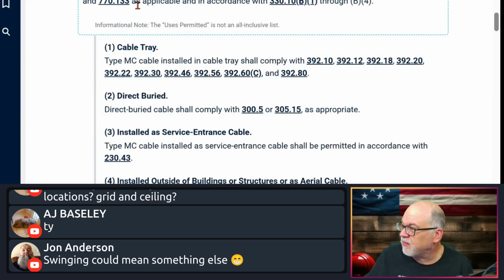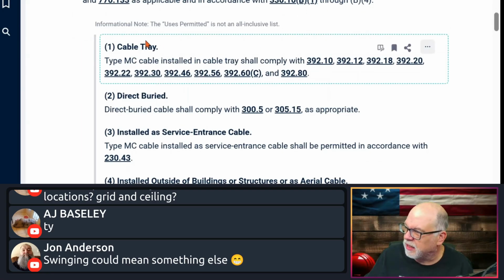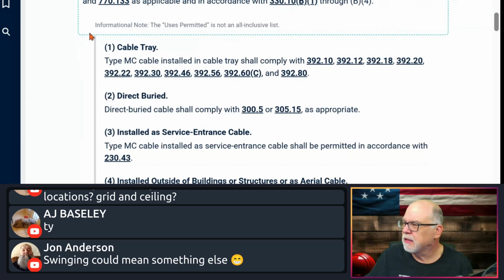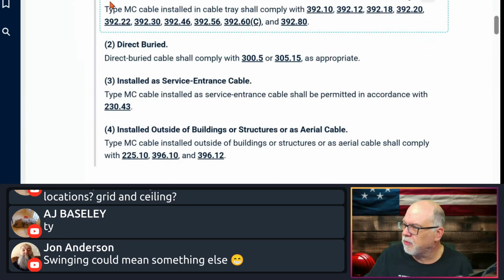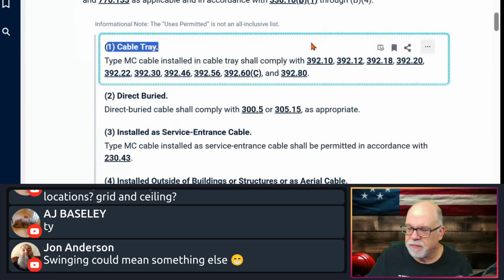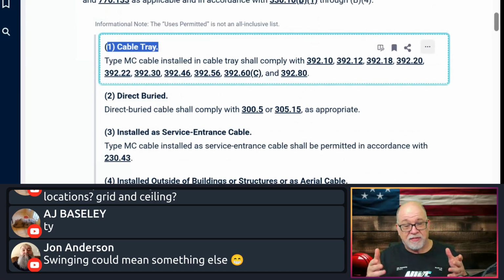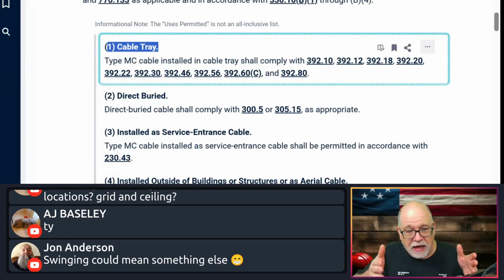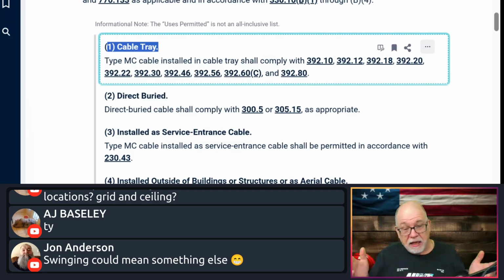All right. So anyway, then it says as applicable and according with 330.10(B)(1) through (B)(4). So we've got to look at each one of these. These are specific uses. Number one, MC cable in cable trays. MC cable installed in cable tray shall comply with 392. These are cable tray articles. So this is talking about other things in cable trays and how you would put them in, the ampacity of conductors in a cable tray, how you can orient them in a cable tray. So this is all saying that it's okay to use MC cable in a cable tray.